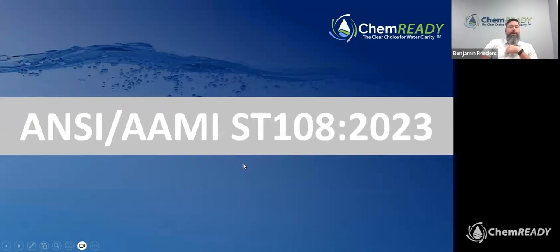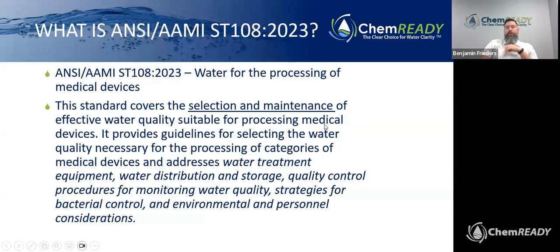So the reason we're all here, ANSI AAMI ST108. So what is the standard and what do you need to know? If you're not aware, or if you've heard of it for the first time, ST108 is water quality for the processing of medical devices. So this standard covers the selection and maintenance of the effective water quality suitable for processing medical devices.